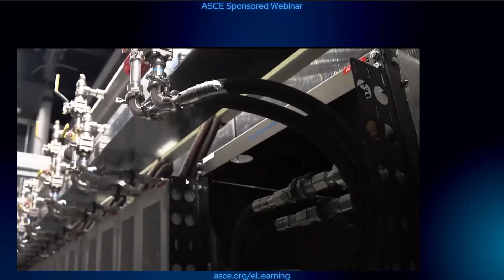The most common liquid cooling method for high-power, data-intensive tasks like AI is direct-to-chip cooling. Here's how it works: chilled cooling liquid starts inside a heat exchanger, which sends it directly to the servers. This cooling fluid flows over metal plates attached right to the processing chips, pulling away the intense heat they generate. Once the heat is absorbed, the liquid flows back to the heat exchanger, where it's cooled and recirculated.